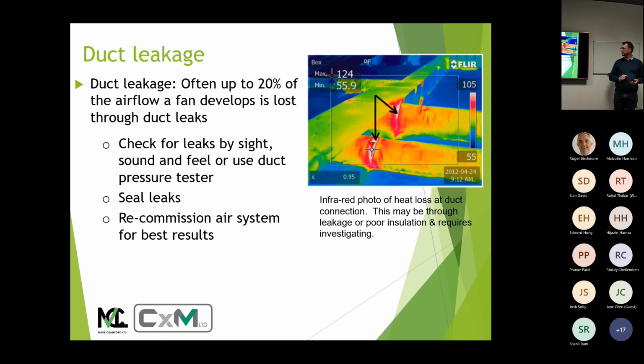We're finding that you're probably putting in something like 20% more air to get the right amount of air out. And that 20% is a lot of energy. A lot of energy that goes somewhere, but not where you want it to go. Normally conditioned air as well. So duct leakage tests are really important at the moment.